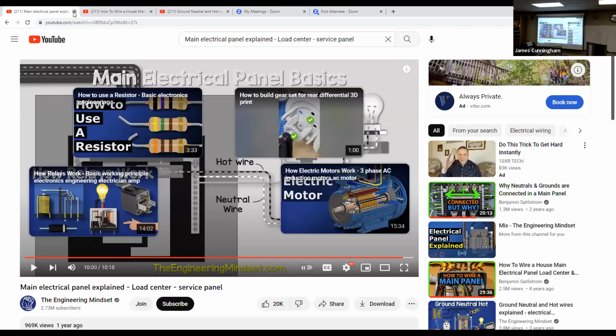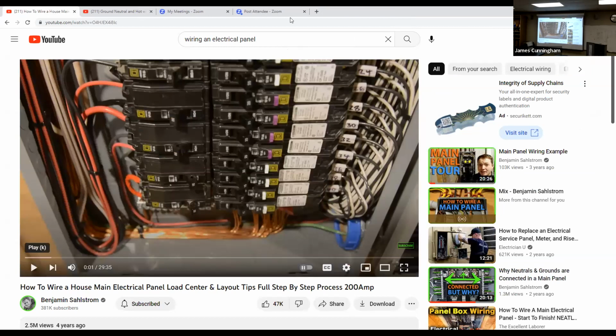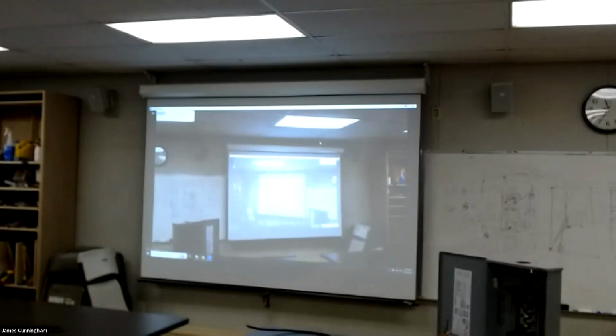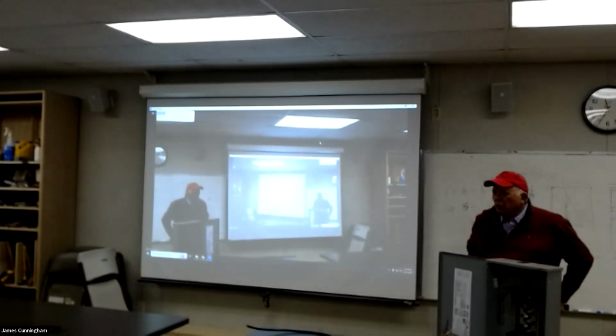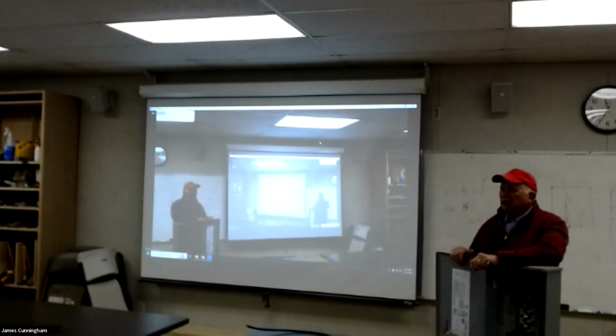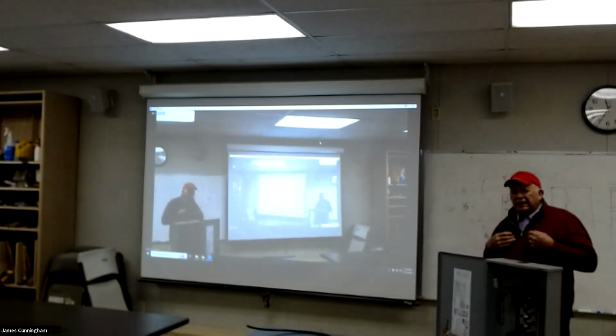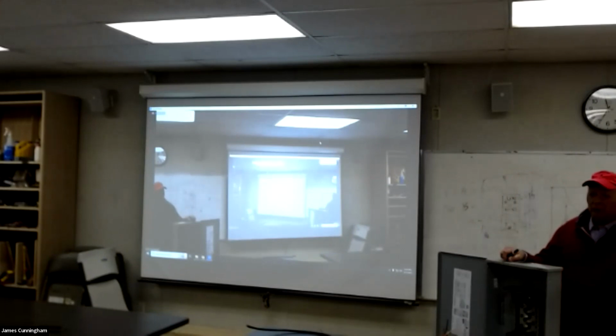I told you before that we have to provide our own grounding. So the Southern California Edison, or in my case, PG&E, they provide the electrical wires, the two hots and the neutral to the electrical panel, but we as a builder or as an electrician, we have to provide the grounding. So you need two types of grounding required by code. You have to have a cold water bond.